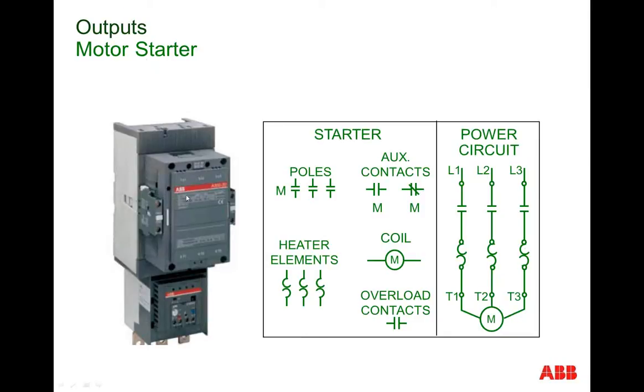So a motor starter not only starts and stops the electric motor, but it protects it by sensing overcurrent situations. Inside this overload are a series of what we call heater elements. They're measuring the current. You can see them in series here with the three phases of power feeding into the electric motor. If we lock the rotor, put a wrench in and goof up the rotation of that electric motor, that rotor may freeze and basically form a short circuit. So current will flow to infinity unless we stop that electric motor. We sense the heat through these heater elements, which are mechanically linked to these contacts that we see here. It'll open up the power circuit to the electric motor, thus protecting the motor. Again, overload relay plus contactor added together equals a motor starter.